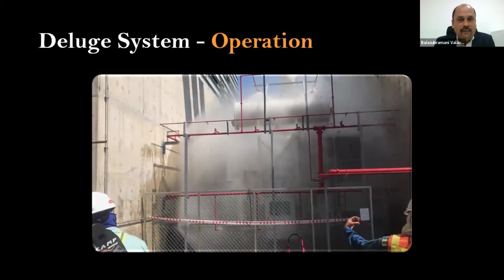In this case, what you have actually witnessed is, if fire happens at a particular place, the water is poured on the entire area, which means the entire transformer. It will not know that the fire is at a particular place. Why? Because you don't know how fast the fire can spread. To put off the fire, being electrical equipment, and to take care of any other critical hazards, this is designed in such a way that the water will be poured on the entire surface.